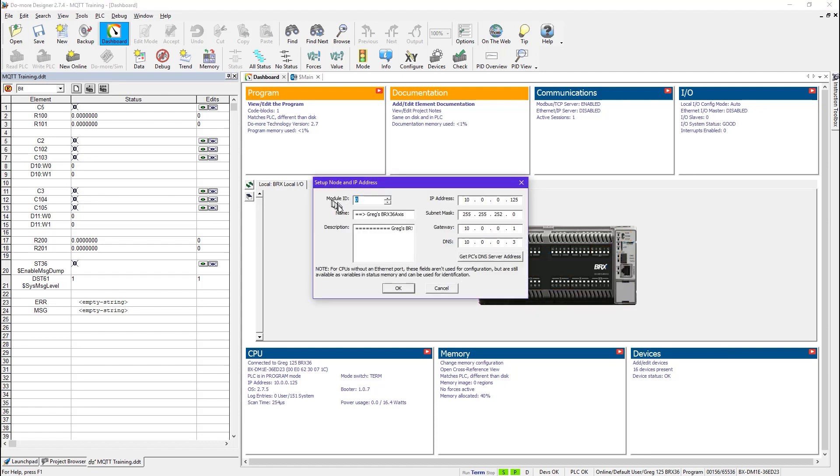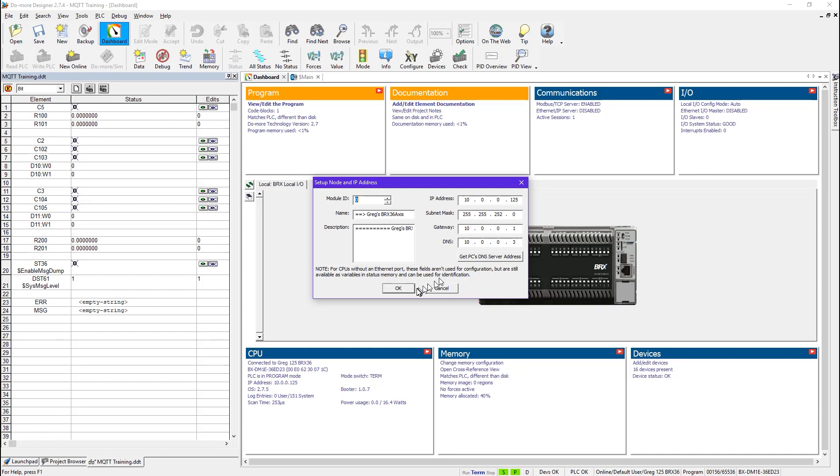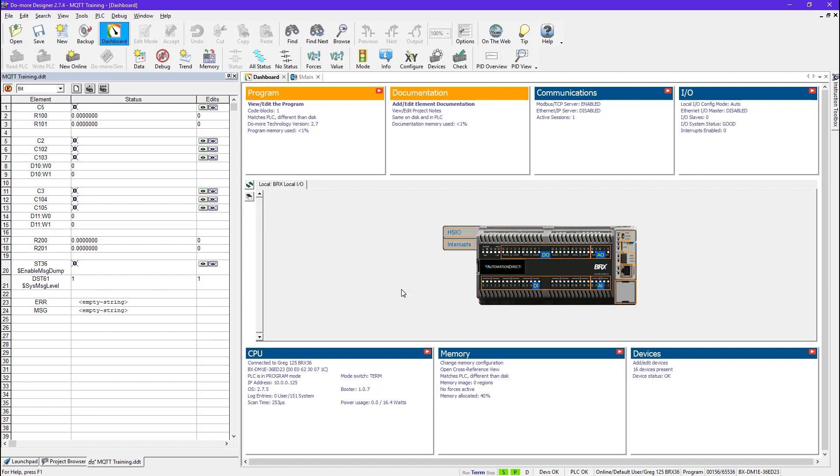you have Module ID, Name, and Description. These are not necessary settings for the MQTT to work. Of course you have the IP address, the subnet mask, and the gateway address, and you also have the DNS address. This is required if you're going to use your broker's name or its URL instead of its raw IP address. Then I would OK this and I would write this down to the PLC.